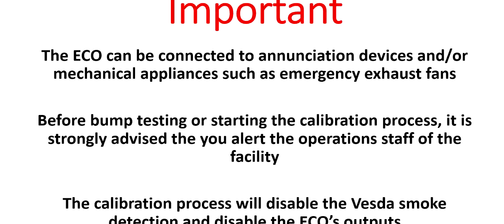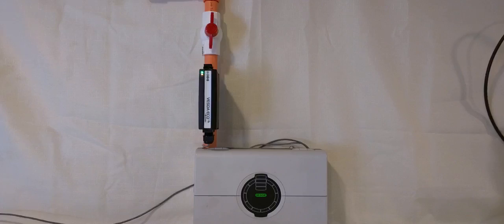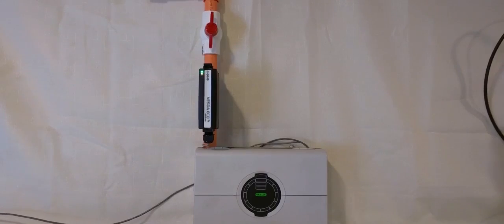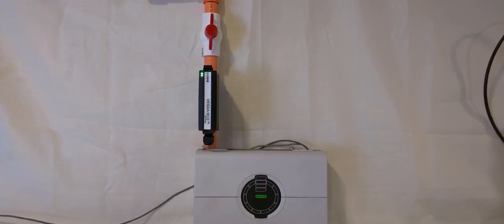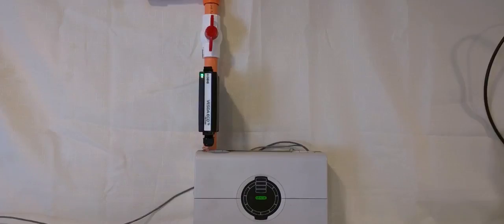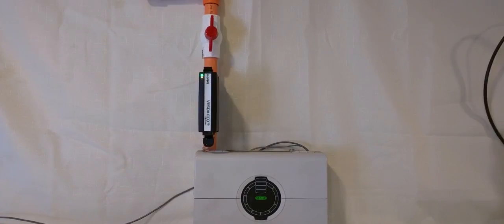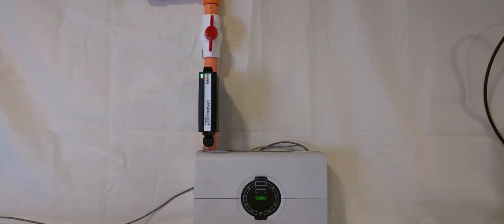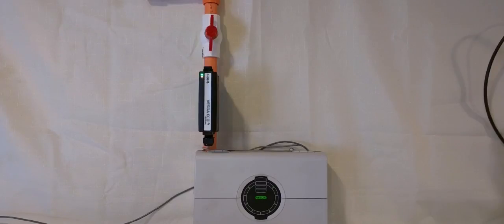When bump testing the ECO, its outputs will be live and will place the detector into alarm. It is important that no air flow is going through the ECO detector before calibration. Air flow through the ECO will dilute the test gas and prevent an accurate reading.